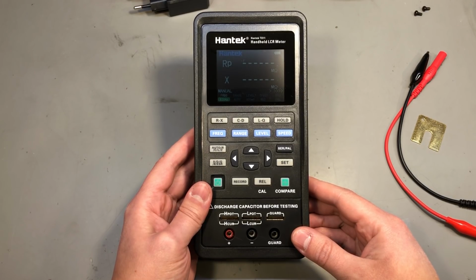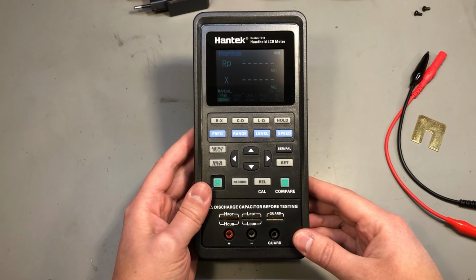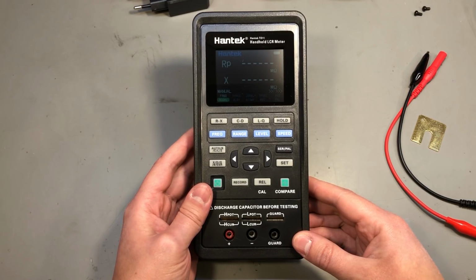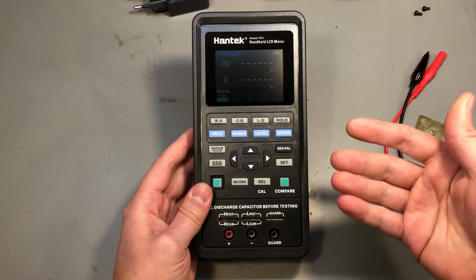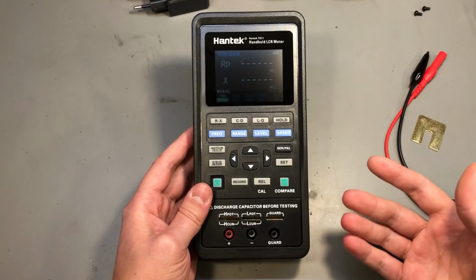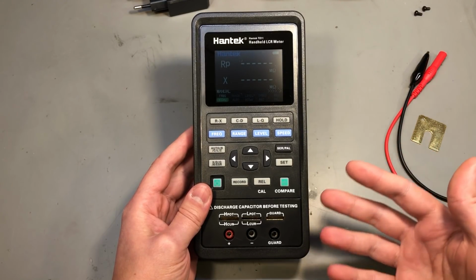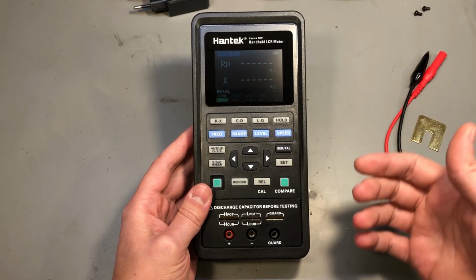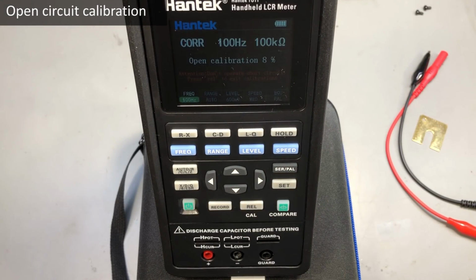Before getting started on some measurements, I will run the calibration feature for both short and open circuit on this meter, and it will cycle through the different ranges and test frequency. It takes a couple of minutes to do that, but I will speed this up on editing.